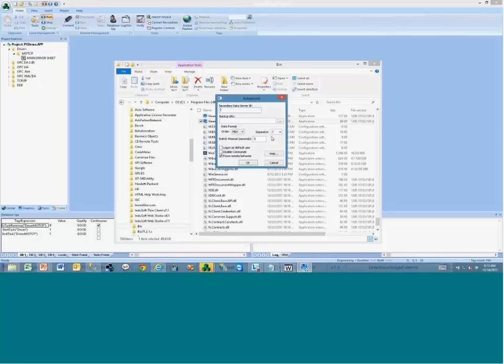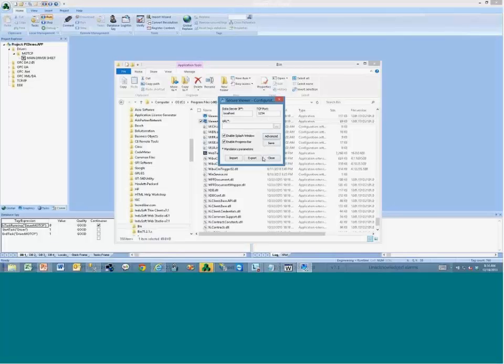And here in the Advanced box, you have the option here to force remote behavior. If you uncheck this checkbox to not force remote behavior, the user should be shared among all the stations, but the tags should remain for each viewer with local scope. So it should allow you to implement what you are looking for.